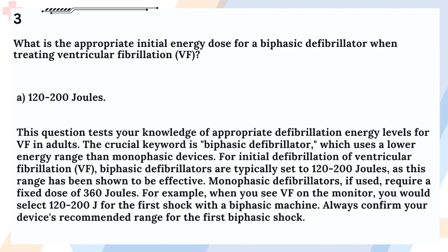Monophasic defibrillators, if used, require a fixed dose of 360 joules. For example, when you see VF on the monitor, you would select 120 to 200 J for the first shock with a biphasic machine. Always confirm your device's recommended range for the first biphasic shock.